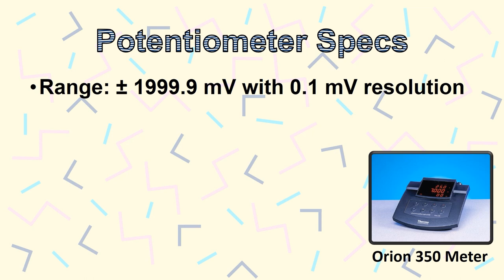For example, the potentiometer can only measure plus or minus 2 volts, with a resolution of 0.1 millivolts. If you try to measure something outside the range, you'll see this error on the display, which also occurs if the electrodes are out of the solution, so don't be alarmed if you see that.